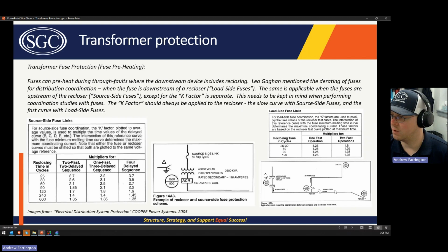So if you have a fault here and you want to make sure that your recloser coordinates with this fuse, as part of the fuse saving scheme, you need to apply these K factors. I think Leo went over this in some detail, but I think he only covered the preheating for distribution fuses.